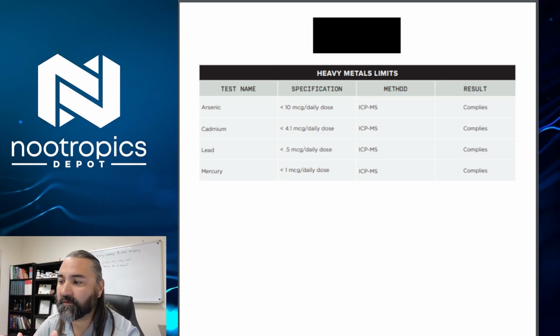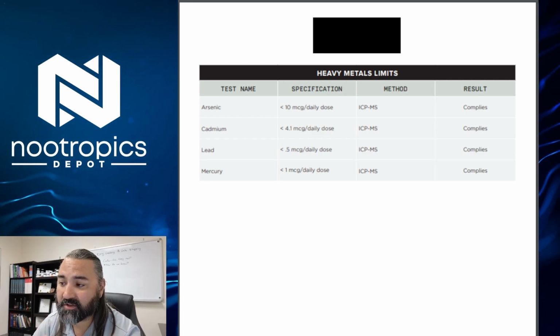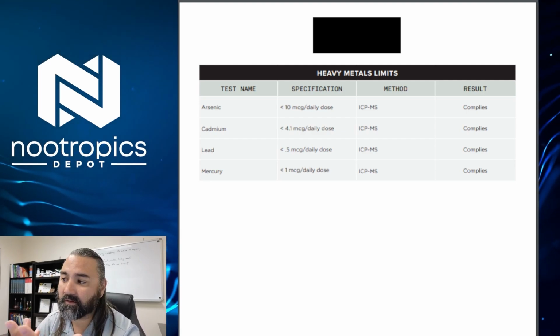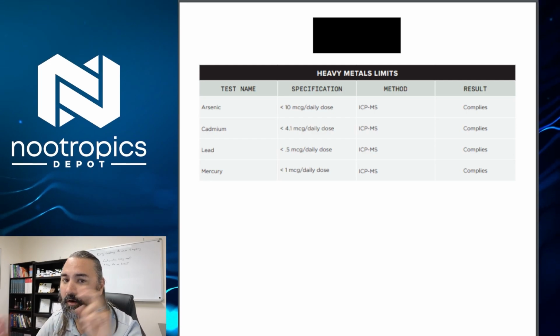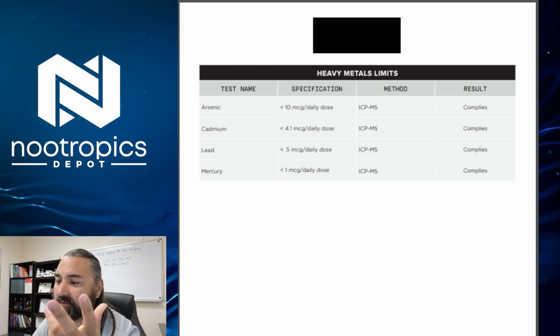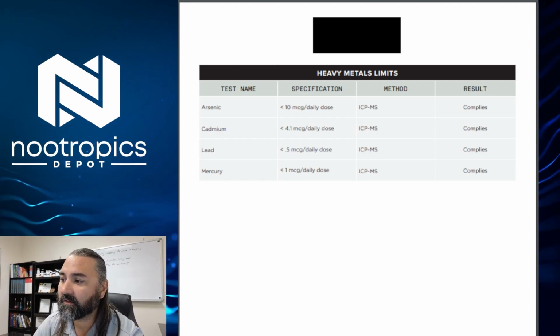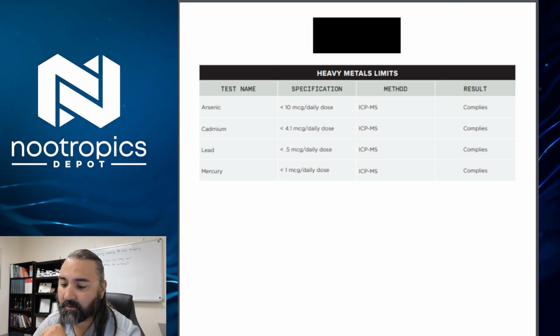You have results, you have specifications, you probably have a valid methodology or method, even though it's not properly stated. Just post the numbers. Like, don't just fake it with words. This is the same problem with the FTIR matches, right? Say what it is that it's matching to and how you're determining what a match is. Same thing here for "complies," especially because you already have the numbers already measured.